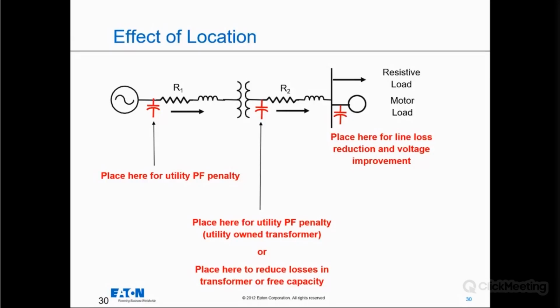So that means what? If you've put a VFD on an air compressor, that means there's harmonics floating around there. And so again, for simplicity and time's sake, we won't go into harmonics and capacitors, but you have to be a little cautious of what you're doing and know what you're doing when you're putting capacitors and VFDs very close to each other. On the other hand, for the large kVAR units, the technology that was driving costs years ago was the controllers. As all electronics have done, controller costs have come down over the years. So that larger kVAR unit sitting outside your plant has gotten more economical, and putting the smaller ones close to motor loads has gotten a little bit more tricky. So that's probably the reason we're seeing the trend of increasing sales for large units and decreasing sales for smaller units.